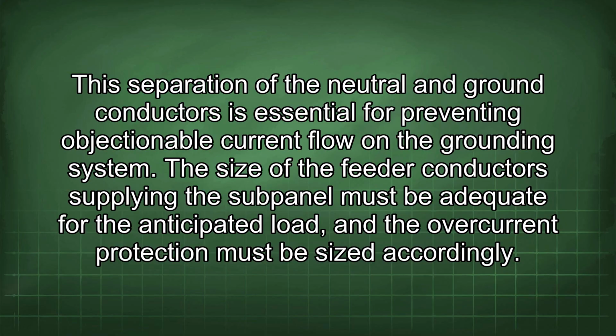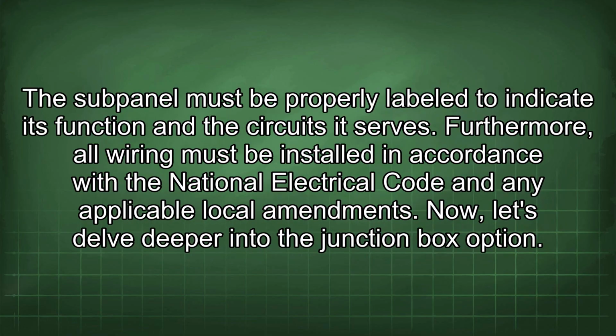The size of the feeder conductors supplying the subpanel must be adequate for the anticipated load, and the overcurrent protection must be sized accordingly. The subpanel must be properly labeled to indicate its function and the circuits it serves. Furthermore, all wiring must be installed in accordance with the National Electrical Code and any applicable local amendments. Now let's delve deeper into the junction box option.